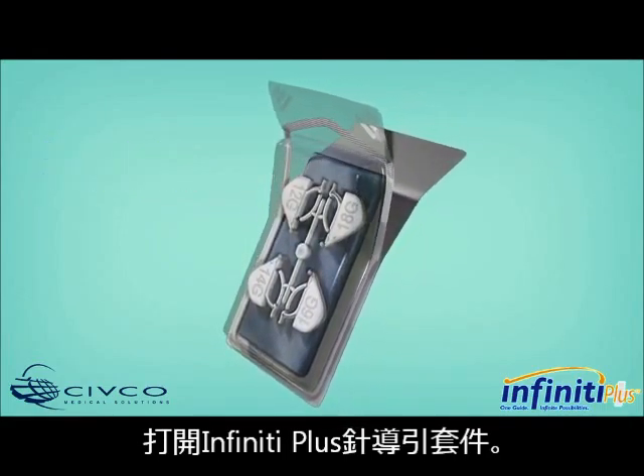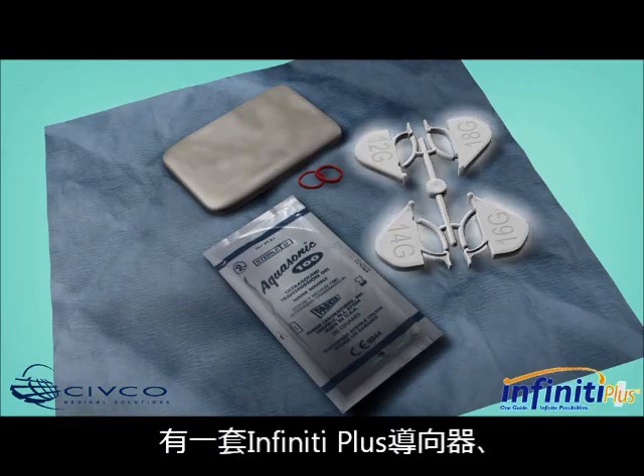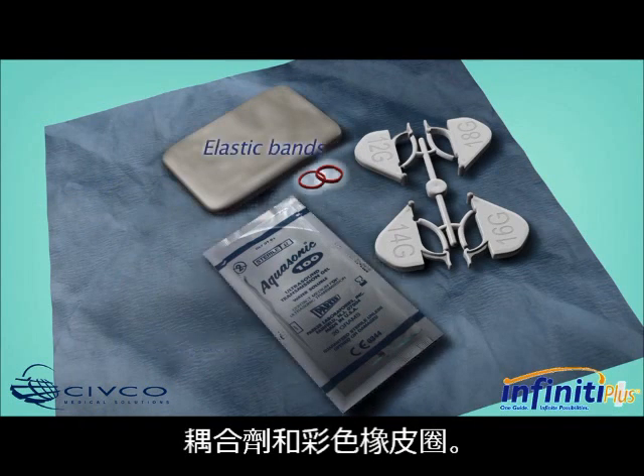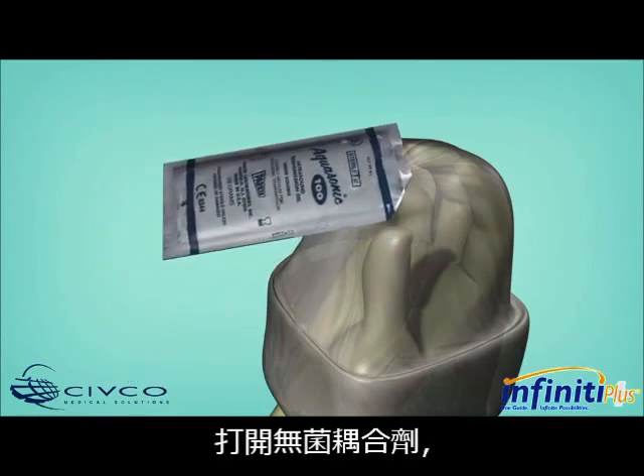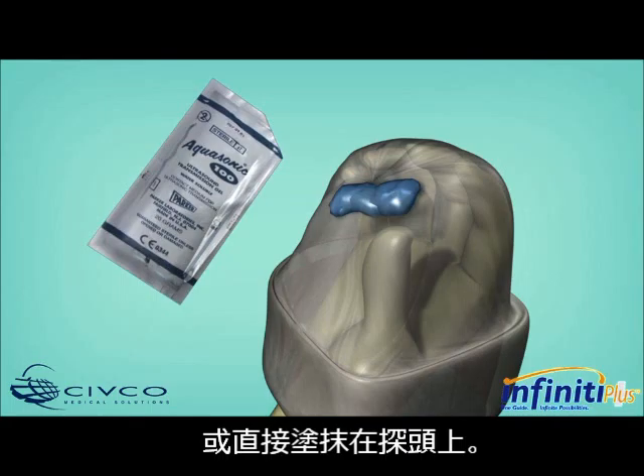Using proper sterile technique, open the Infiniti Plus Needle Guide Procedure Kit. Inside each kit, you will find an Infiniti Plus Needle Guide, a protective SIVFlex transducer cover, gel packet, and colored elastic bands. Open the sterile gel packet and apply gel to the inside of the SIVFlex transducer cover or directly onto the array of the transducer.